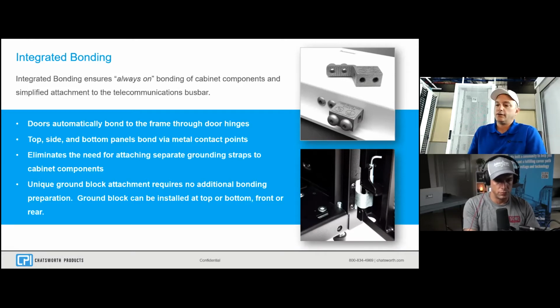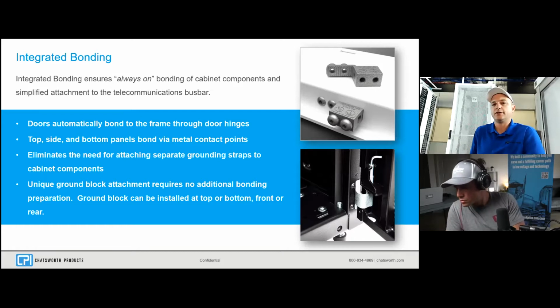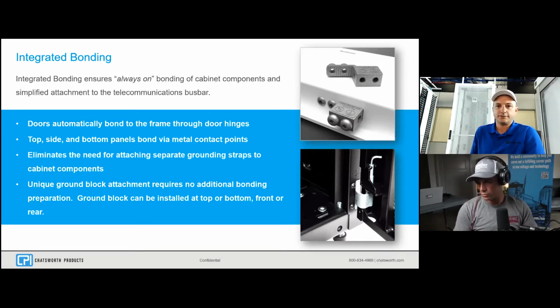The end result is this always-on bonding. You're no longer trusting that whoever last took that piece off - and it's real common, especially on day one installation, to take side panels off and take doors off - remembered to plug that wire back in. It's always on.